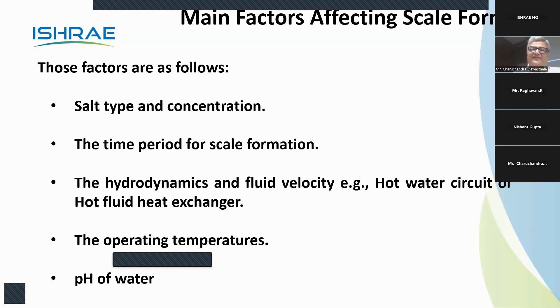Operating parameters and operating temperatures: the higher the temperature, the more the scaling tendency. And pH of water, as we have already seen, if pH is low it is corrosive in nature, and if it is very high then it is scale forming in nature. So both ways it affects.